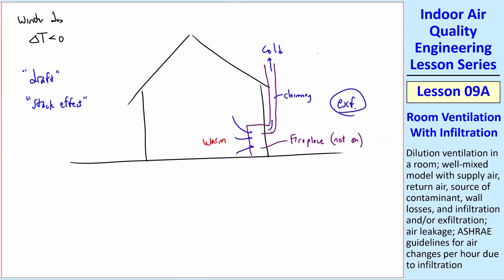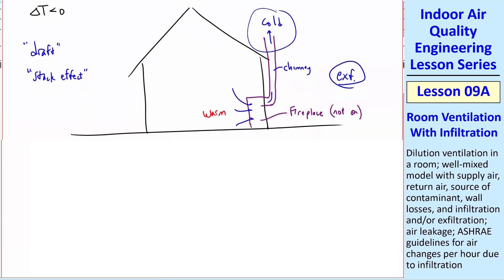The other thing is, if you have wind, if this is our stack coming up and you have wind blowing over it and that air is coming out, what's going to happen is because of the Bernoulli effect, you have a low P here. So it's going to draw even more air out of the house. So there's more exfiltration.